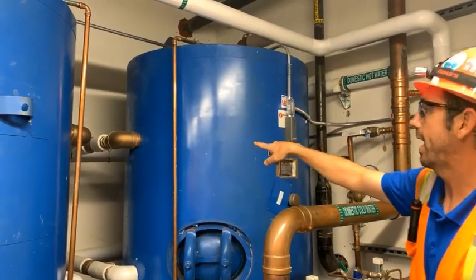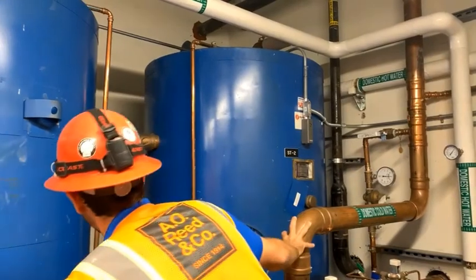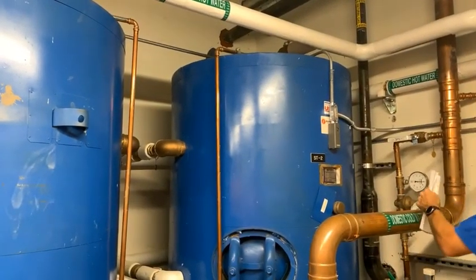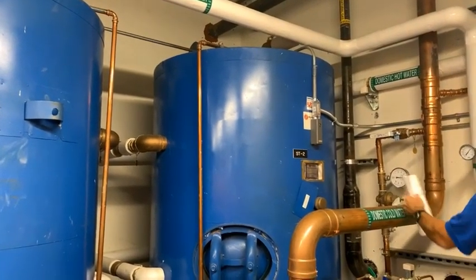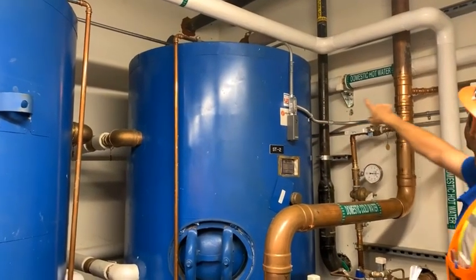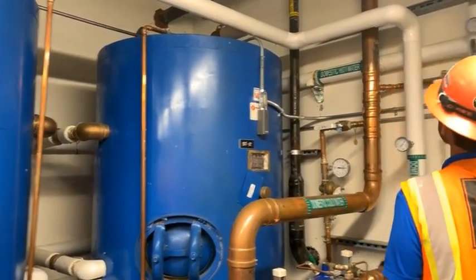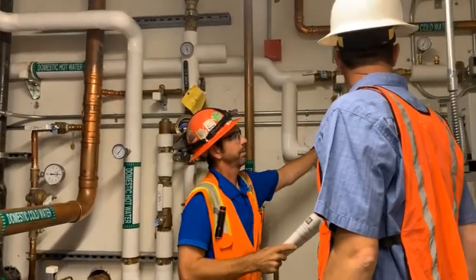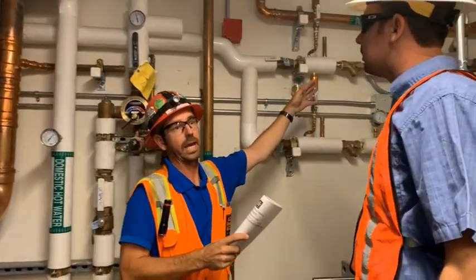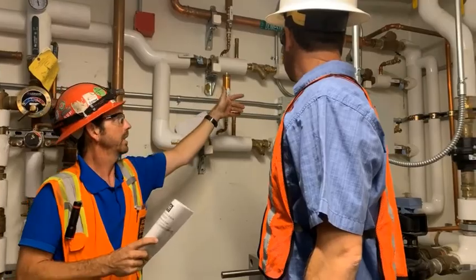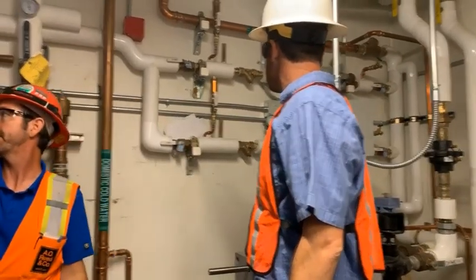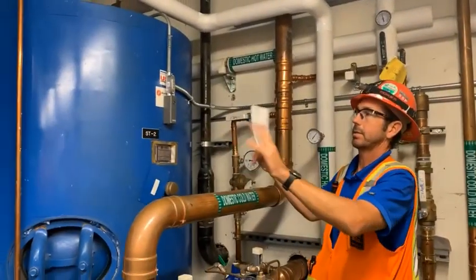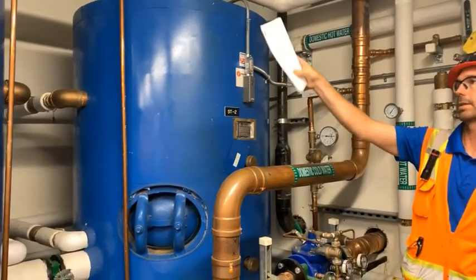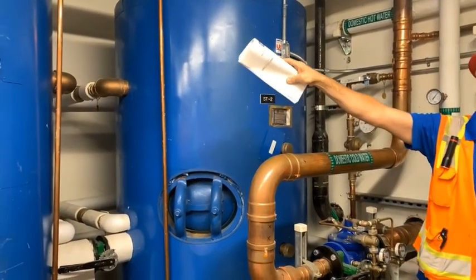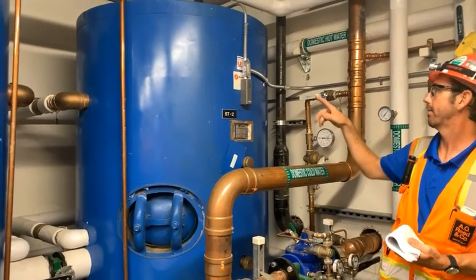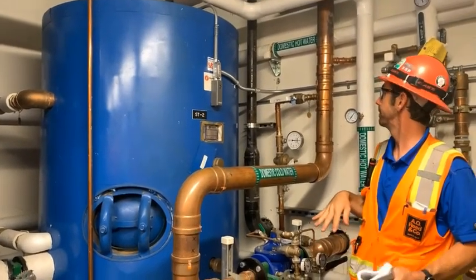The hot water comes out of the, sorry, bear with me here. It's been a while since I've actually looked at this piping. The hot water comes out of the tank. We have 2 circ pumps. These pumps are not redundant. They can both work at the same time. Each pump has its own aquastat. There's one on the front of the tank. And since these tanks are spun to get the piping coming out the middle, the other aquastat's on the other side of storage tank 1, okay? So each aquastat runs a pump individually.